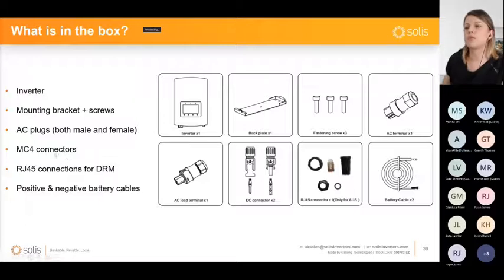And we always strongly recommend that when you're connecting your PV, you always use the MC connectors that come with the inverter, and don't use any others, because it's very important in terms of compatibility. If these connectors don't match up 100%, it might lead to damage to the PV inputs, because there's going to be an increase of resistance in there. Even if you have crimped them tightly and right, the resistance will rise, and it may cause damage, melting of the connectors. So always use the ones that came with the inverter, because that's why they're there.